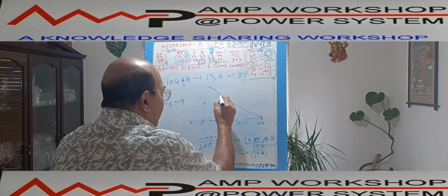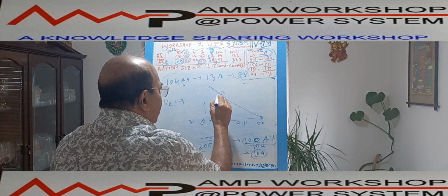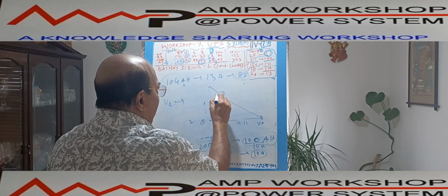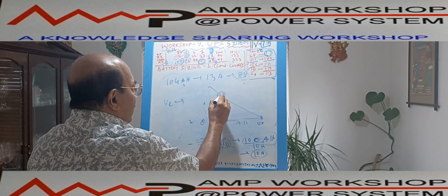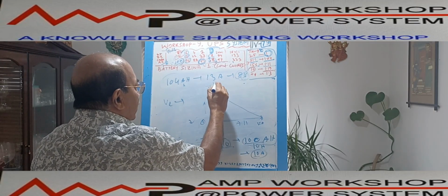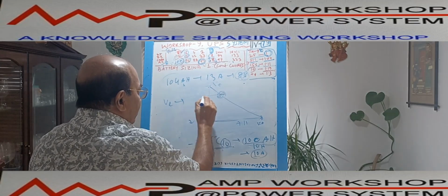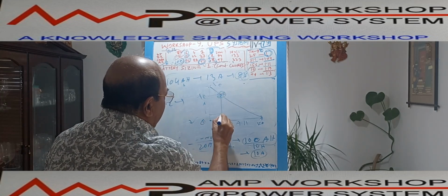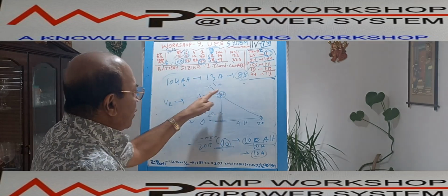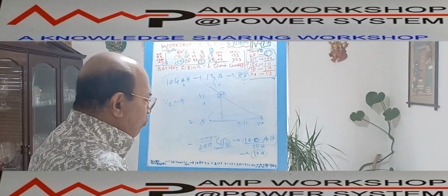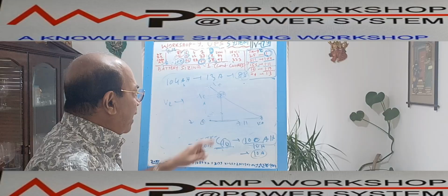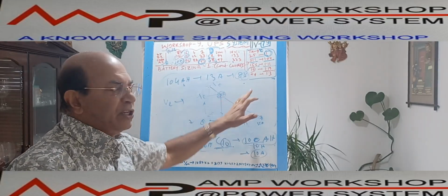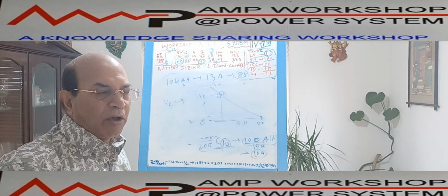Now if I end the voltage over here, suppose this is my voltage. At this voltage I am dropping. This is the no load voltage, it is V0, okay? And this is the VE. If we drop at this voltage, how much ampere hour will I get? I will get this ampere hour. I am not getting the full ampere hour. So we have already said that we cannot go VE below 90% of the VN nominal voltage.